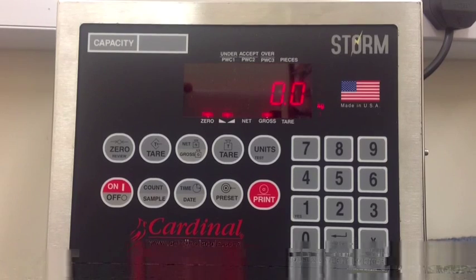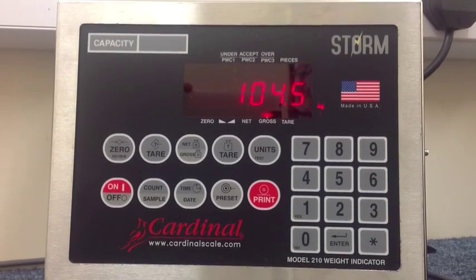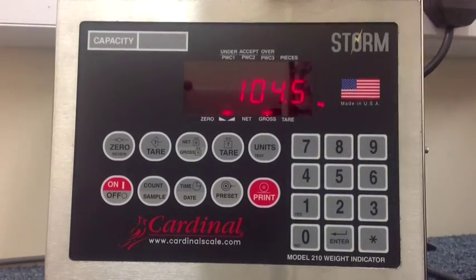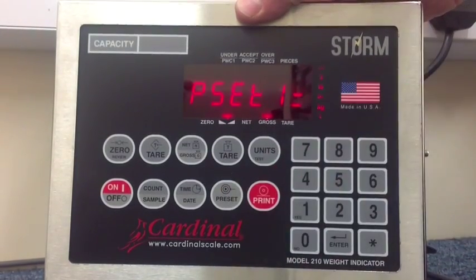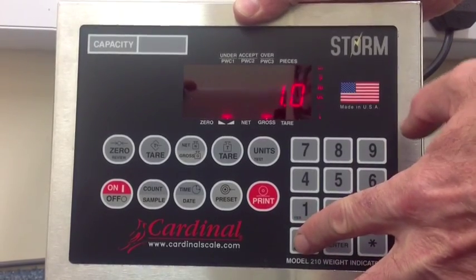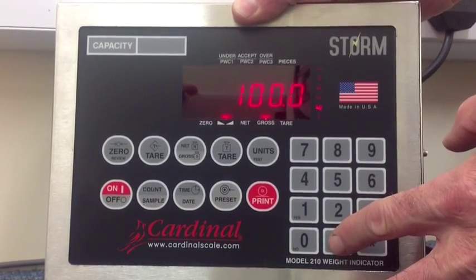Loss in weight with an audible alarm on the Cardinal 210. Place the IBC or container on the scale. Press the preset key to enter the target weight required. Here we're entering in 100 kilos. Press enter.